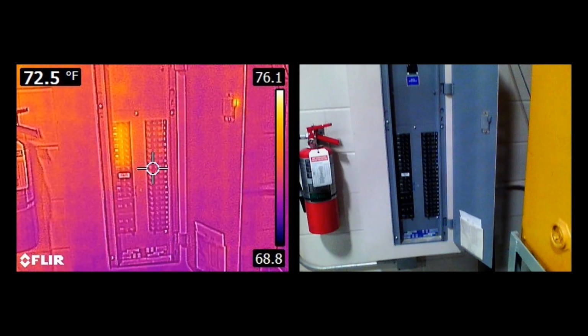These images show a circuit breaker box and give us a good idea of some things we could look at. We see that the temperature in the upper left-hand corner of the box is warmer than the rest of the box. However, when we look a little closer at the temperature gradients, we see that the high in this image is only 76 degrees and the low is 69 degrees. So we're not really too far off, but it's something to consider when troubleshooting.